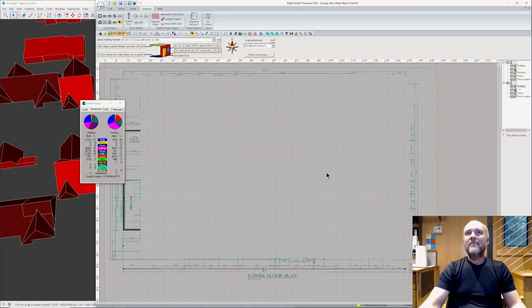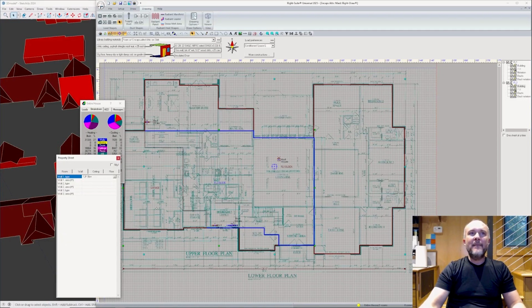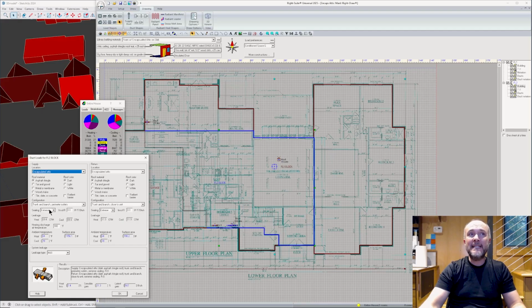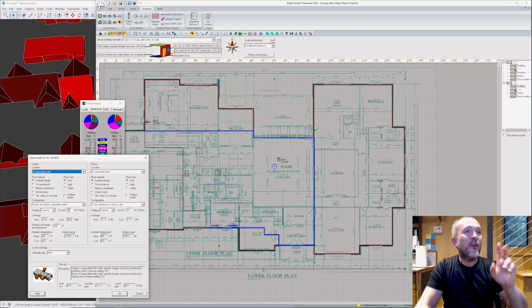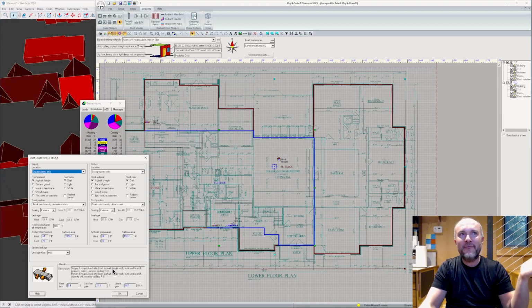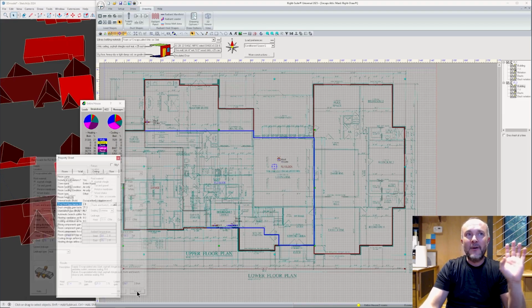If we select both of these and I come back into the same exact place, first of all, you can see we do already have a duct heat loss factor, and that is with extreme tightness with, I'm being nice, an R8 insulation, which is the best insulation. The other one had an R6 on it because you frankly don't need to worry about anything aside from condensation if the attic is actually at the right temperature. So I'm going to get back out of here.